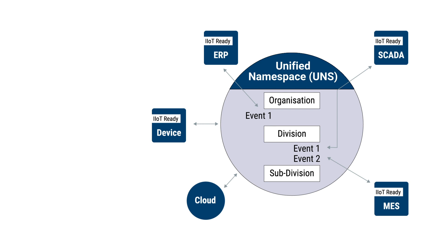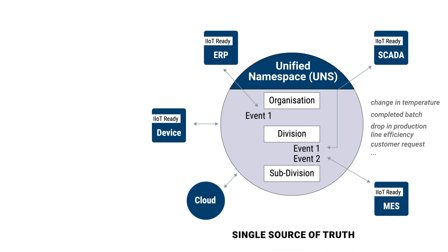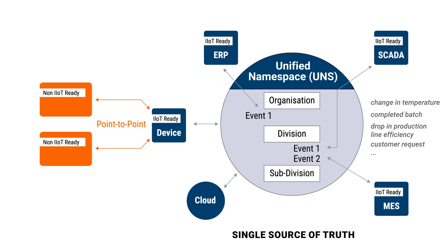Events may, for example, represent a change in temperature, a completed batch, a drop in production line efficiency, or a customer request under a specific level of your hierarchy. This naming arrangement provides a single source of truth containing all the data about the structure and current state of your entire enterprise. In a nutshell, this is what the unified namespace is all about. All components that can communicate using IIoT protocols, such as MQTT, point to a central repository of information that holds your hierarchical enterprise structure and publish their events under a category in which it makes sense for that data to live. Components that are not IIoT-ready are placed behind an IIoT gateway that publishes information to the relevant categories on their behalf.